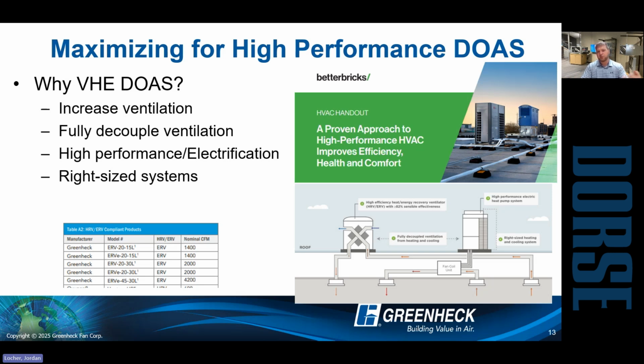There are two real drivers of it. I have a couple of screenshots here from the NEEA Better Bricks group, which is an incentive agency pushing this technology. The reasons to use this technology: one, we want to increase ventilation in our spaces. If we get more fresh air into our buildings, everyone is going to be happier and healthier. Two, the drive is to fully decouple that ventilation load. Typically ventilation is one of the biggest energy hogs in the building, so by decoupling it and using very high efficiency equipment, we can drive down that energy usage.